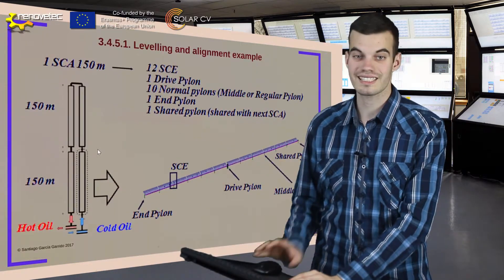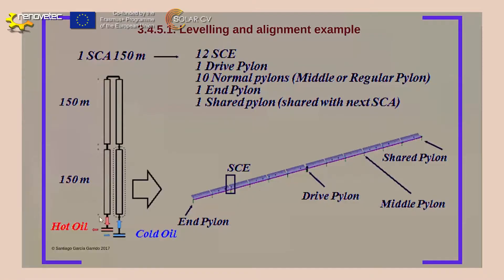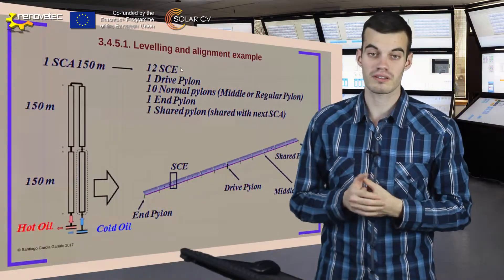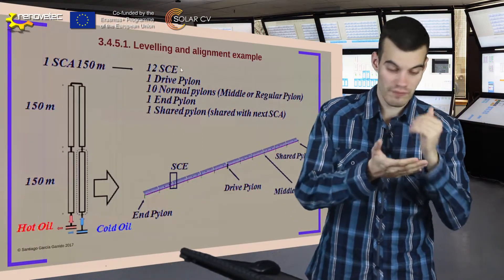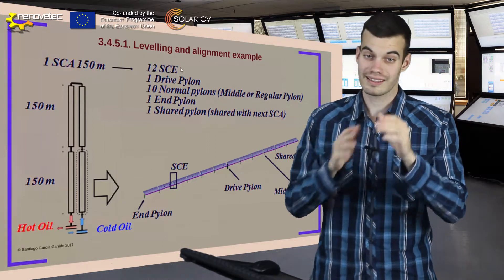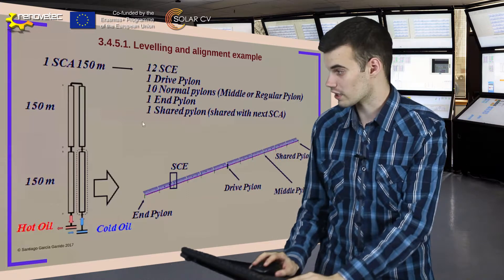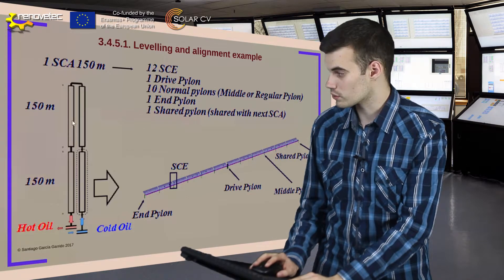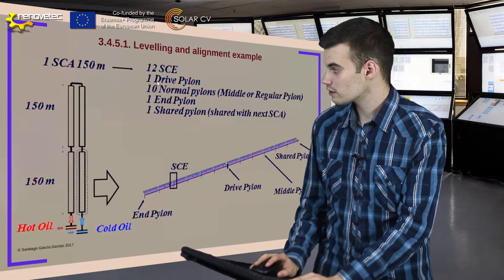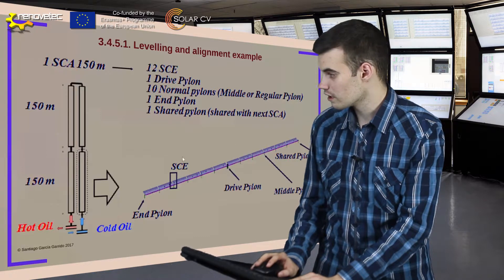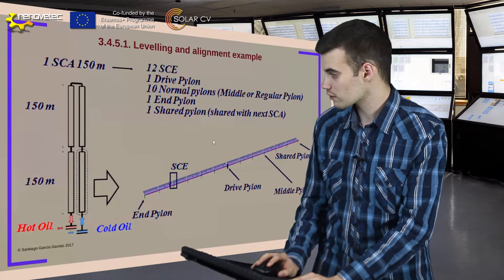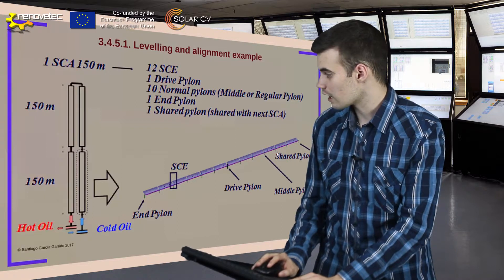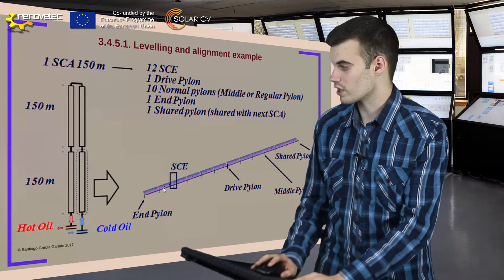Finally, here we can see an example of a loop. Each collector has a length of 150 meters and each collector has 12 SCE. Because of what we discussed previously, if each collector has 12 modules, the loop is going to have four collectors — and here we can verify this concept: one, two, three, and four collectors. Here we can see some drive pylons located between both collectors and end pylons, and some middle pylons which are going to join the different modules.